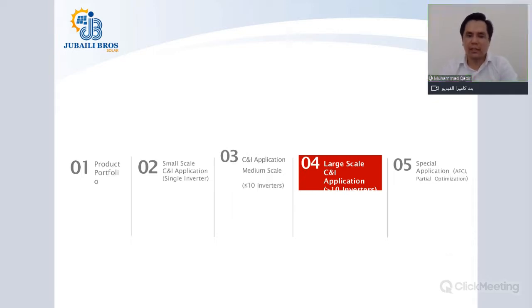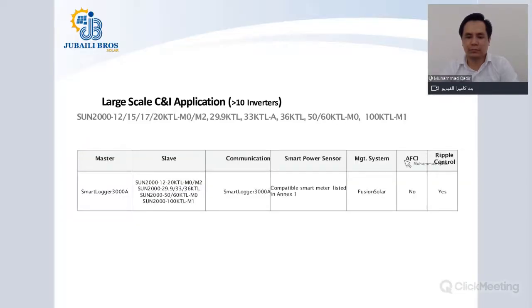Coming to the large scale C&I application. Large scale is categorized as projects where you will be using more than 10 inverters, and the inverter models can be from 12 to 100 kilowatt low voltage inverter sizes. Here, the master device will be the Smart Logger 3000A only. The slave can be any inverter model from 12 to 100 kilowatt size.